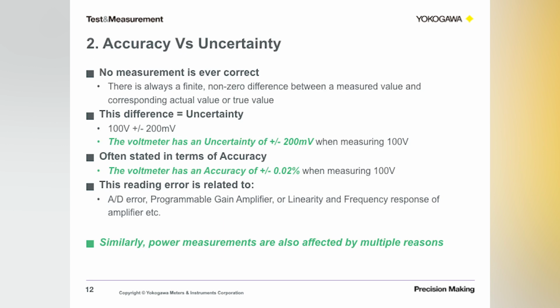Now, you may ask, what is uncertainty, right? In reality, no measurement is ever correct or exact. There's always going to be an unknown or a finite or non-zero difference between a measured value and the corresponding actual value or a true value. So this difference is what should be stated as uncertainty. Based on my previous example of 100-volt measurement, the measurement has an uncertainty of plus or minus 200 millivolts when measuring a 100-volt signal at a 100-volt range.